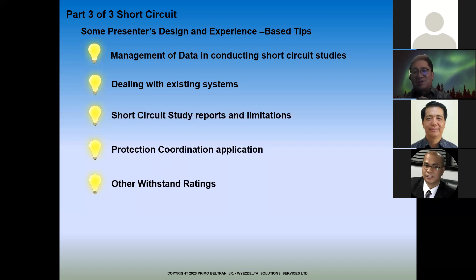Is the MVA method okay? I find it okay, I've used it too. But I only use the MVA method as a thumbsuck - if I'm not buying equipment yet, still at the very beginning of a project and just want to estimate, MVA method is fine. The only problem with the MVA method is that you're not able to separate R and X, and because of that you're not able to get the X over R, which you need to evaluate or specify the interrupting rating, the peaks, or the close and latch capability and everything.